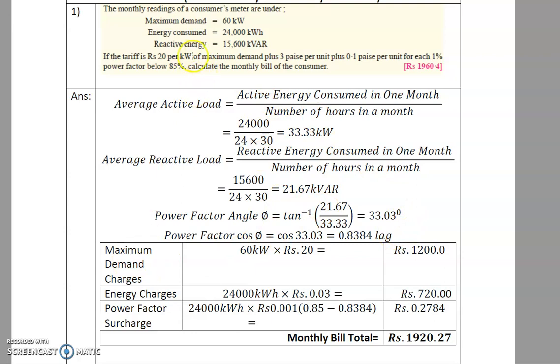Now we calculate the bill. Maximum demand charges: rupees 20 per kW, and maximum demand is 60 kW, so 60 × 20 = rupees 1200. Energy charges: 3 paise per unit, so 24000 kWh × rupees 0.03 = rupees 720.